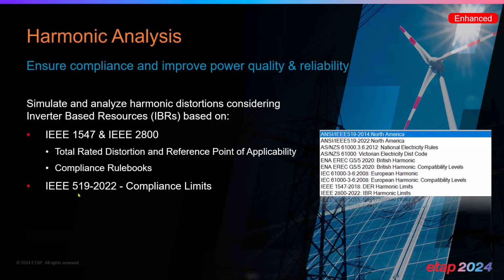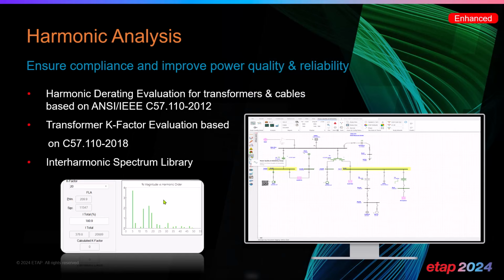We've also improved the harmonic analysis module to comply with the new changes in IEEE 519/2022, including the updated compliance limits and updated definitions in terms of point of interconnection and point of applicability or compliance. Within harmonic analysis, we've also enhanced the derating evaluation for transformers and cables based on ANSI C57.110. And you can also use ANSI C57.110 for transformer K-factor evaluation in order to ensure that you have the right capacity of transformer when you're applying it to a system that is rich in harmonics and making sure that the transformer MVA capability can withstand the current going through the system in addition to the fundamental current.